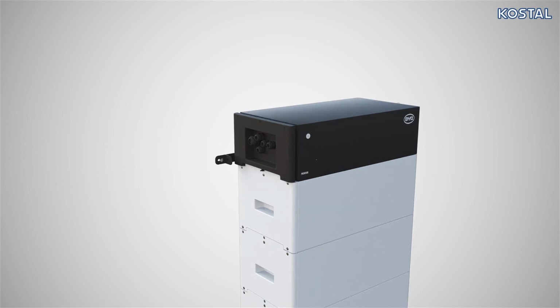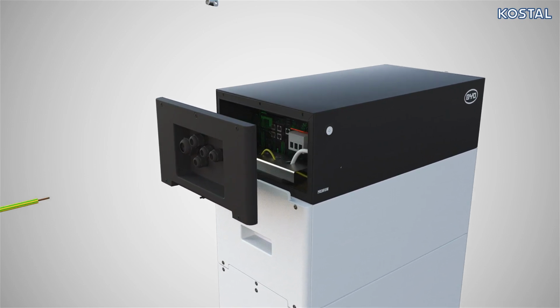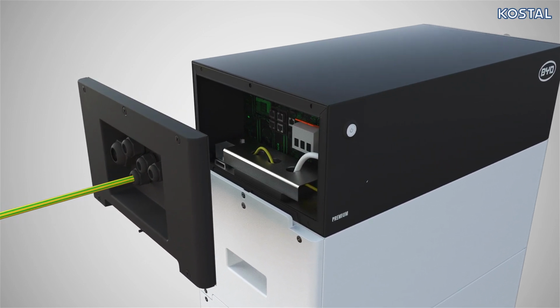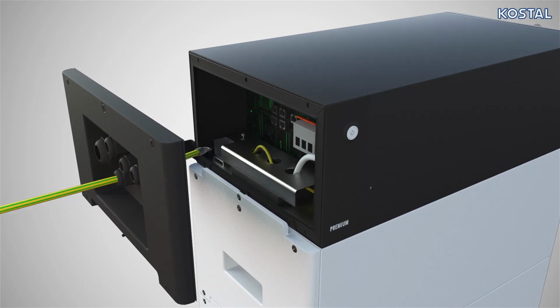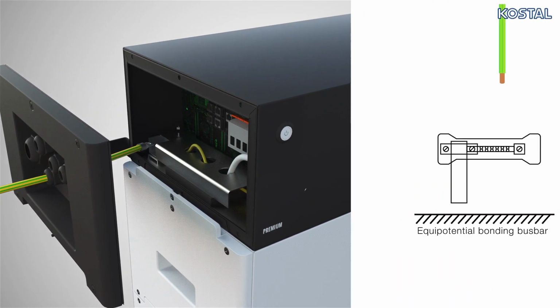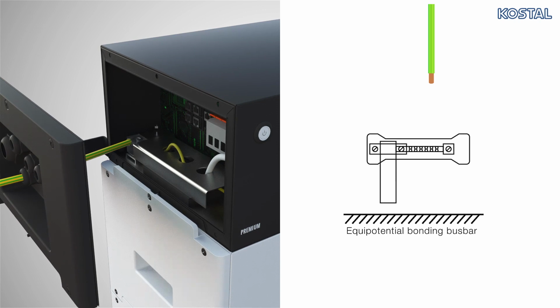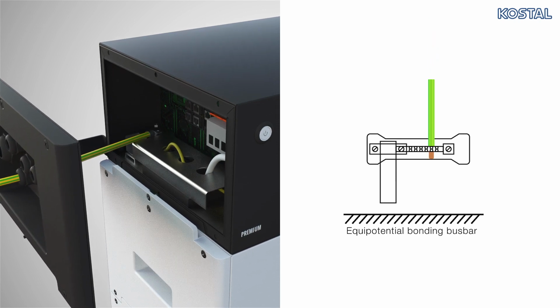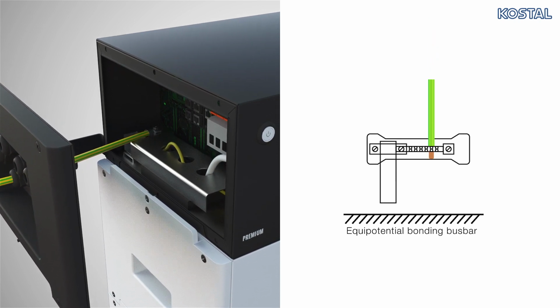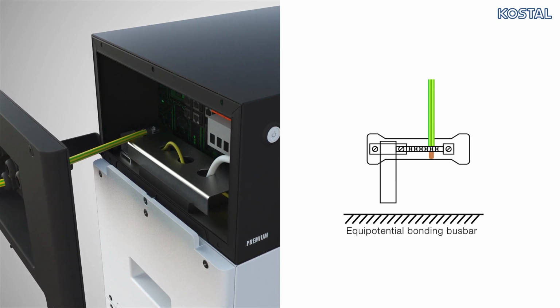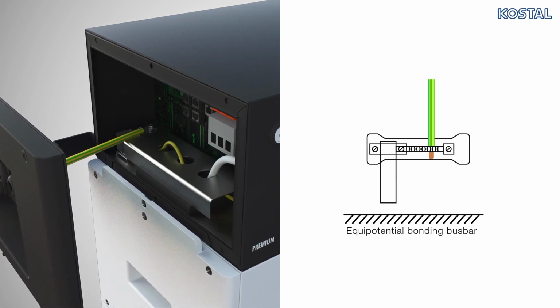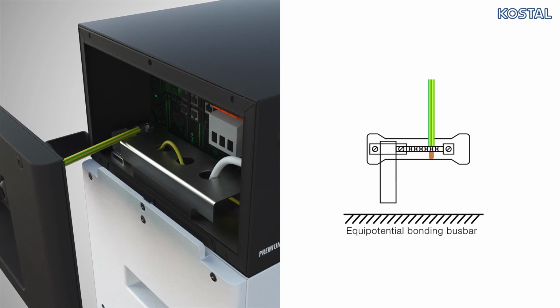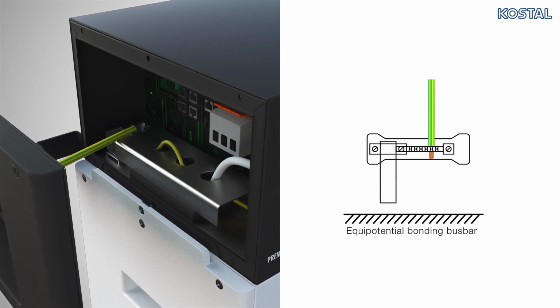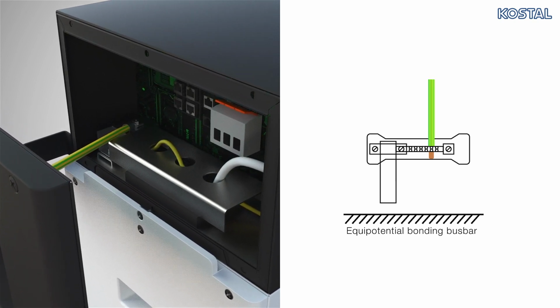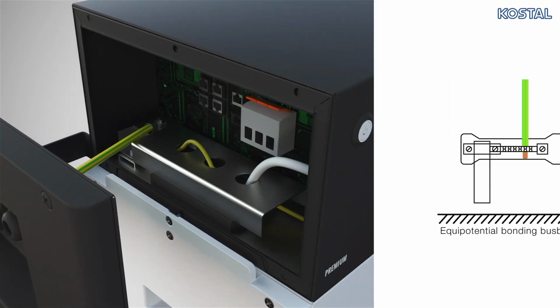Now guide the connection cables through the cable glands provided on the terminal compartment cover of the management module. Start by connecting the PE connection of the battery to the equipotential bonding bus bar. Note, it is absolutely essential that this connection is made. There must be no potential difference between the PE connection of the PLENTICORE and the battery. Be particularly careful to ensure that all cables are installed and routed in an EMC-appropriate manner.